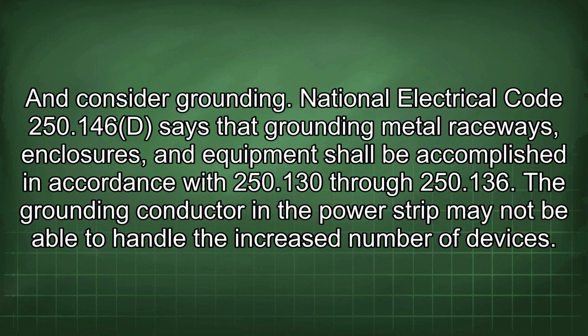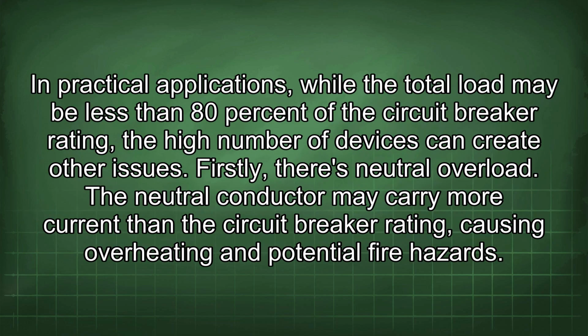And consider grounding. National Electrical Code 250.146 says that grounding metal raceways, enclosures, and equipment shall be accomplished in accordance with 250.130 through 250.136. The grounding conductor in the power strip may not be able to handle the increased number of devices. In practical applications, while the total load may be less than 80% of the circuit breaker rating, the high number of devices can create other issues.